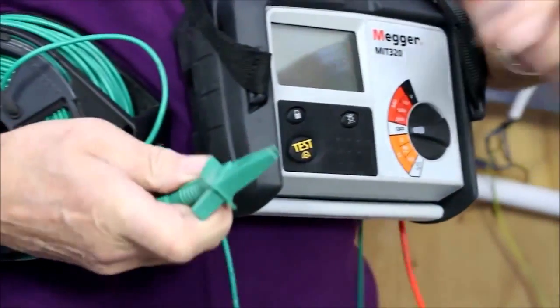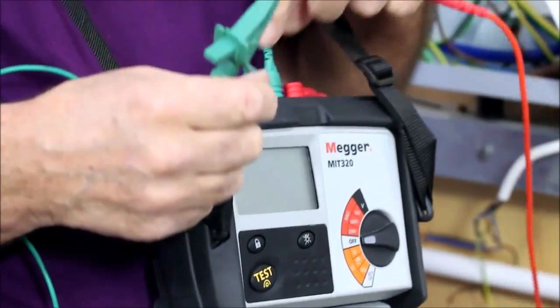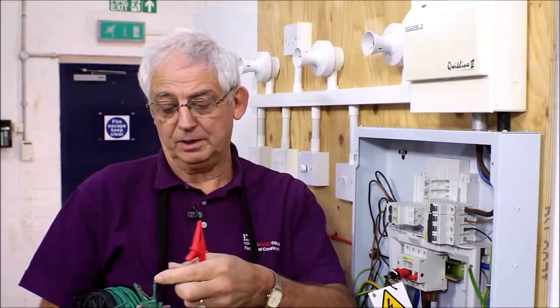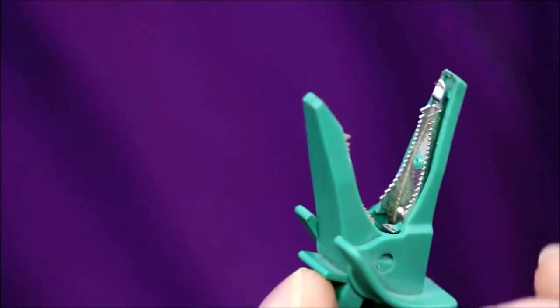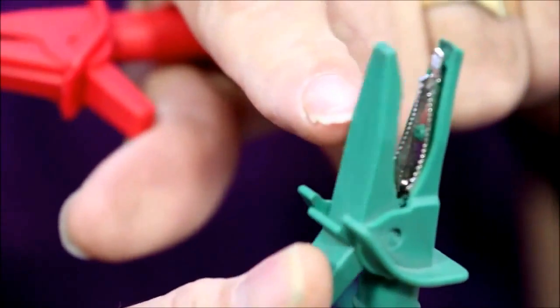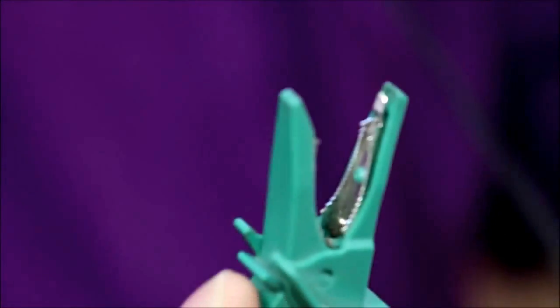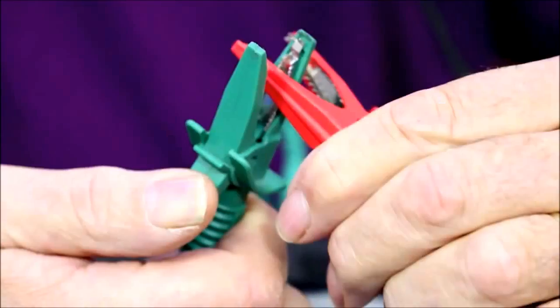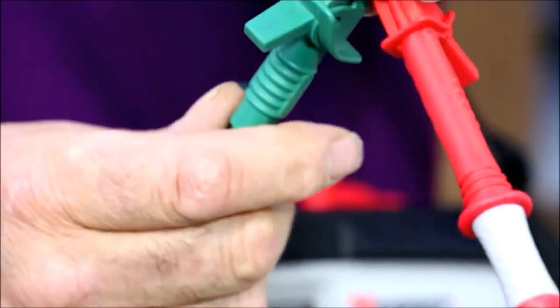So what I do is I join the two ends together, the crocodile clips together, having plugged one end of the lead into the test meter. The important thing when you're zeroing leads is to ensure that you get the crocodile clips connected around the right way. If we look at a crocodile clip, we can see that this is a solid connection through there, whereas the jaws on this side are on a spring. We need to make sure that when we connect them together, we get the two solid connections touching each other. It might sound silly, but actually, we're measuring very low resistances here.